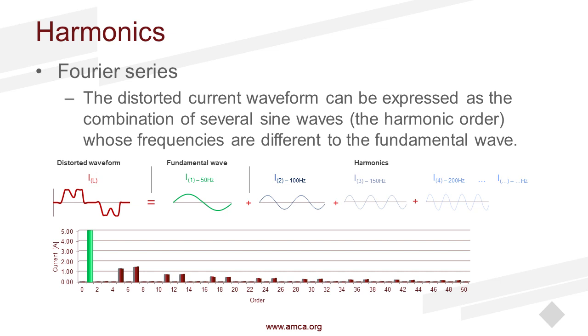Ideally, you would just want to see your fundamental wave, this perfect ideal sinusoidal wave. But when you have all of these nonlinear loads, your power electronics, this is where you're starting to see the harmonics, the different frequencies. When you add all of these together with the fundamental wave, this is where you get your distorted wave. So the green is good, and then all of the red bars are the harmonics, the things that you would want to mitigate, get rid of, reduce.